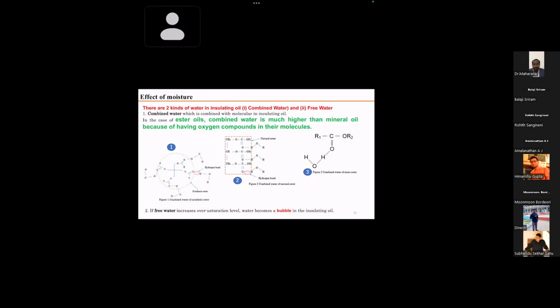Compared to mineral oil, ester fluid has different physical and chemical properties - for example, its viscosity is much higher than mineral oil. Should the design structure of the transformer be changed according to ester fluid's physiochemical properties? Can we just replace mineral oil inside existing designs available in the market, or should we redesign the pressboard stacks, the distance between stacks for good circulation to reduce winding temperature, and other conditions, when implementing ester fluids inside transformers?